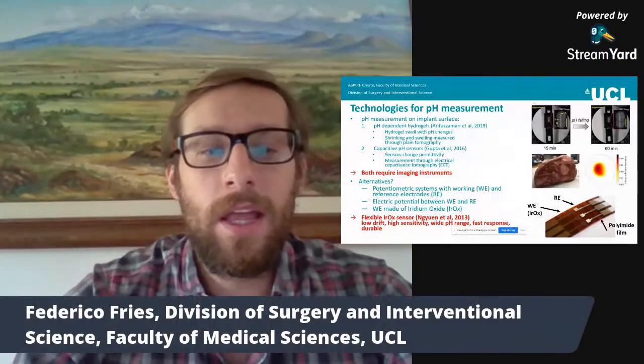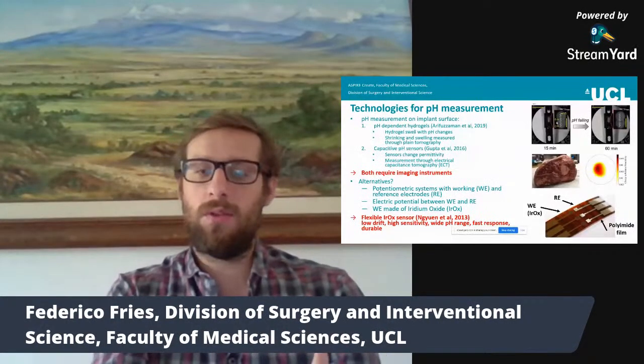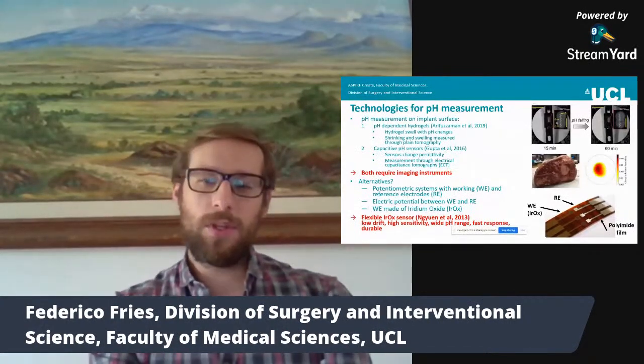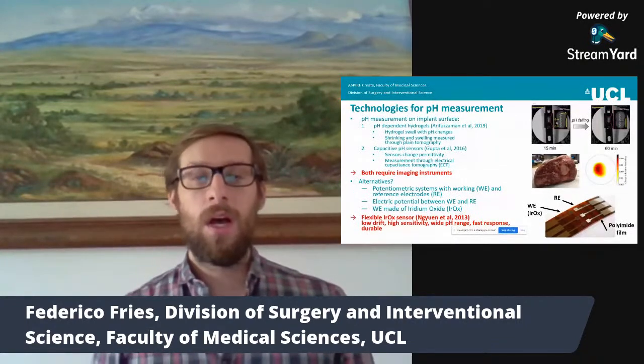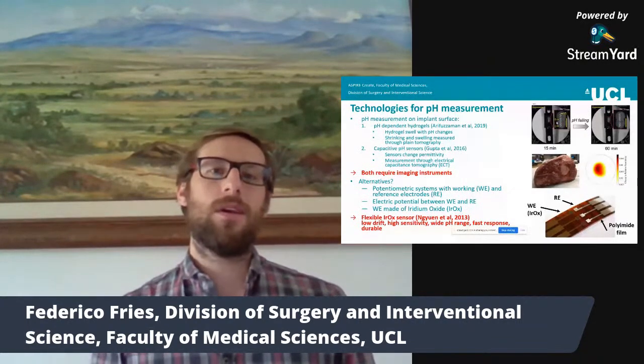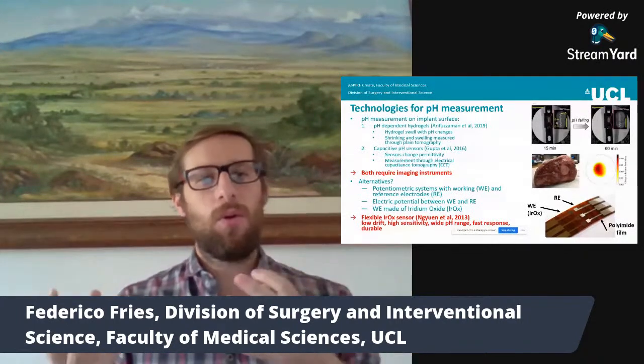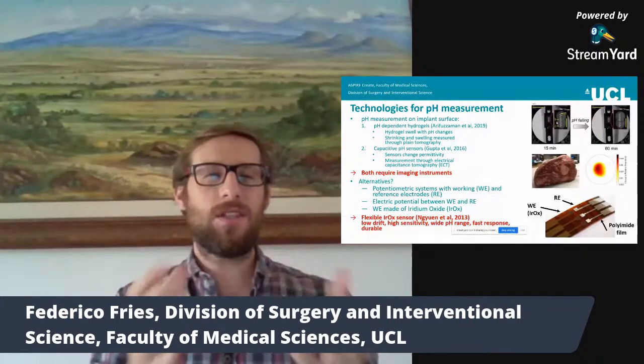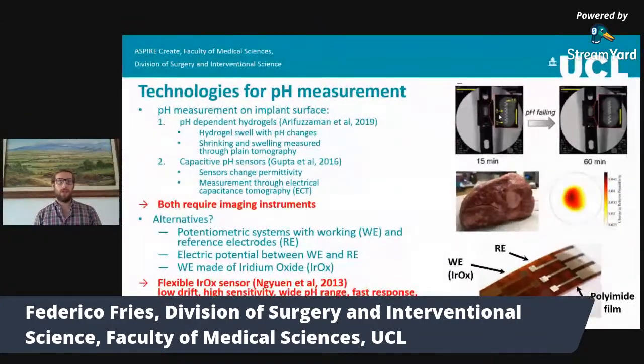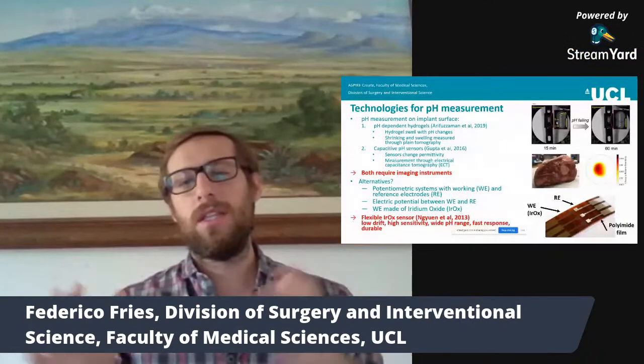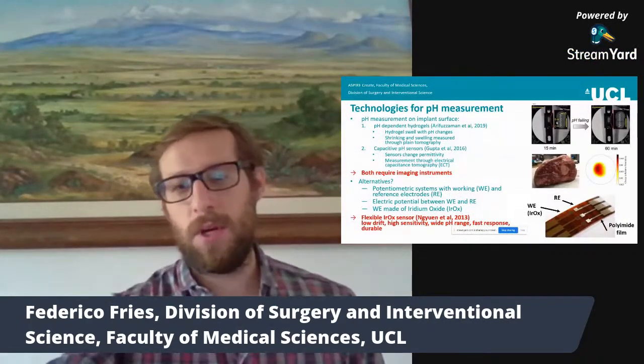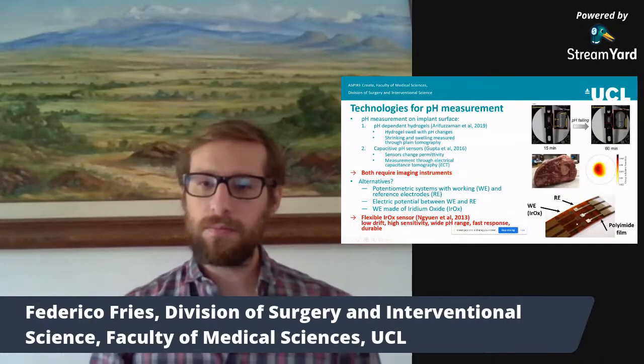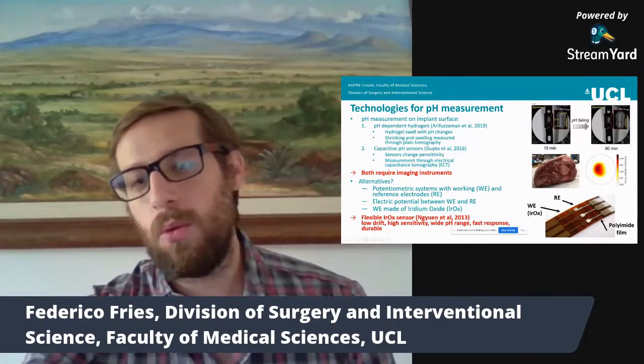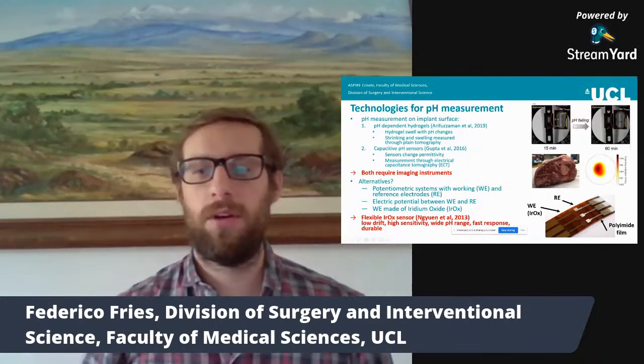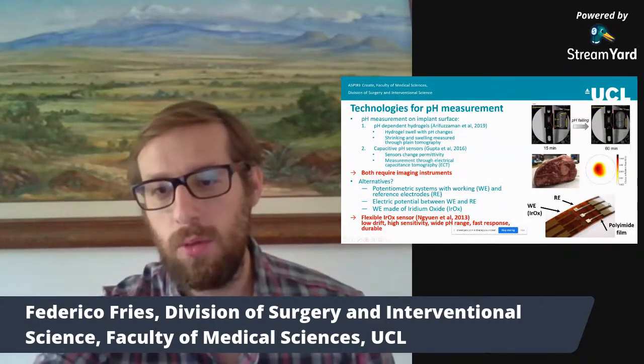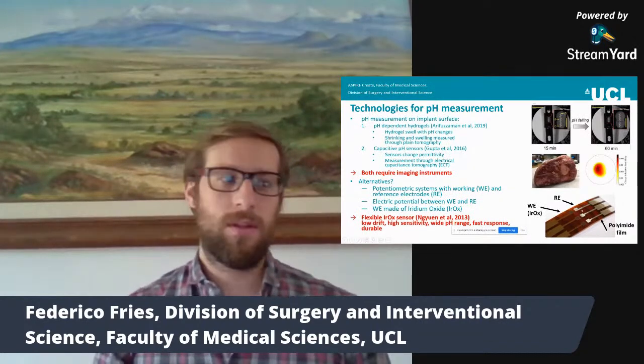And the one that I chose in this case was one proposed by Nguyen in 2013. The reason for this is because it is flexible. Why is this important? Because implants have very odd shapes. So if you have a stiff sensor, it is hard to integrate into the implant. If you have a flexible sensor, this could be a lot easier. And here's an image of this sensor on the corner. You see the working electrode, the reference electrode, and the film over here. This is a very small sensor. This area is 2 by 2 millimeters, so it also allows you to integrate it almost everywhere.